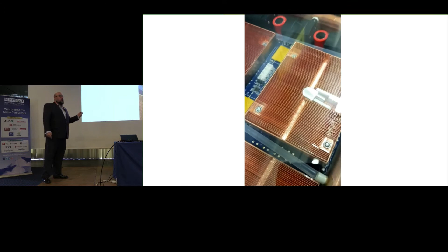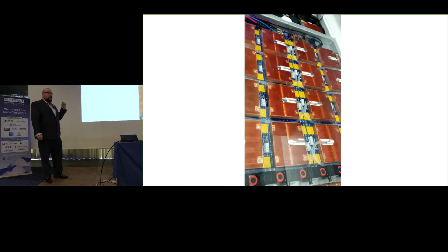Whereas a lot of people use mineral oils and things like this, very suboptimal. By reducing the volume of coolant, you'll notice we've got heat exchangers at the back. The coolant stays only in a single server tray, goes through the heat exchangers, and comes out the rear to be dumped. But that's a secondary coolant, which is a standard water glycol mix.